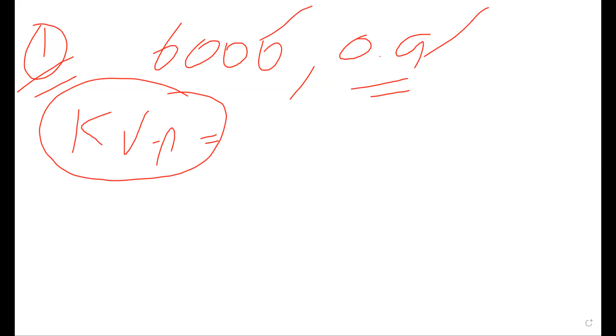6,666.67, or 6,667, you can take any digit ahead. Can you calculate kVAR for generator number one? kVA equals 6,000 divided by 0.9, correct, because we are talking about generator number one now. What will be the kVAR?